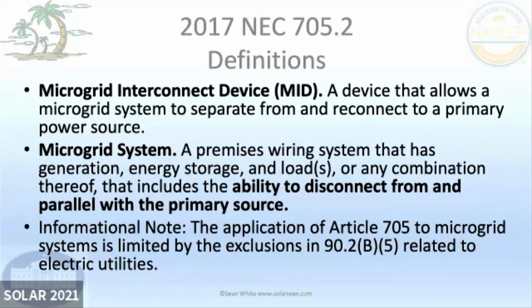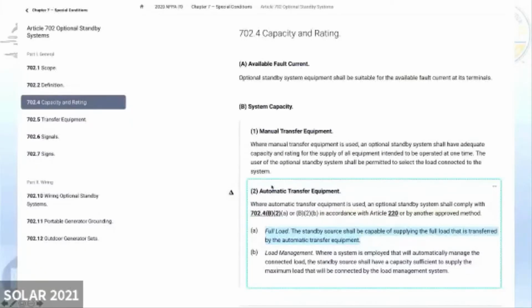Then we have a microgrid system. This has the ability to disconnect from the primary power source, which would be the grid. This is also something they're probably going to change in the NEC, because it makes it sound like a microgrid has to be able to connect to the grid. But it doesn't, because you could live on a mountain and have a microgrid. People say the excuse is, well, maybe when the grid comes here someday, I still have the ability to do that.